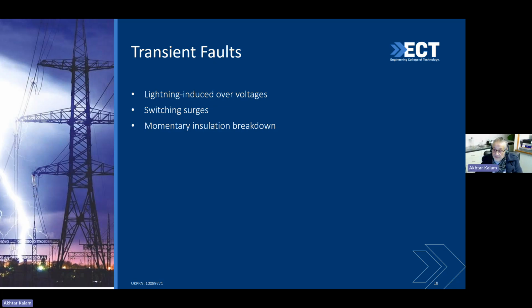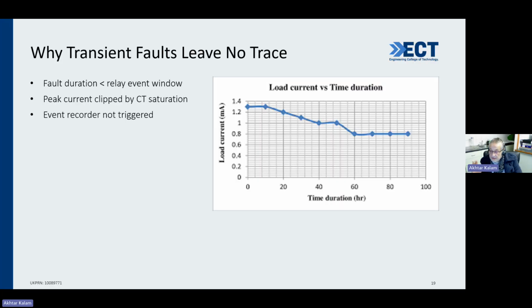As far as the transient fault is concerned, my friends, they leave no trace, because the duration of the fault is a lot lower than the relay event window. I told you, for a very short period of time. Peak current could be clipped by the CT saturation. You've heard about that BH curve. And the event recorder did not do any triggering.